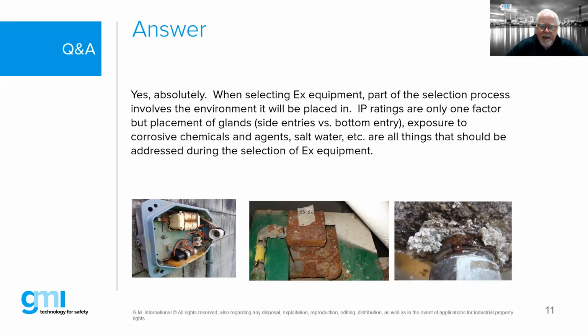Obviously, in the example on the left-hand side, a light fitting was leaking or something happened, so we had some corrosion on the inside there. The picture on the right-hand side is a nickel-plated brass gland, or actually, I don't know if it was nickel-plated or not, going into an aluminum enclosure, and you can see that you had some serious chalking. This is a big issue with cable glands going into aluminum enclosures in a high saltwater environment. So you can start to see degradation very quickly if we don't provide suitable protection, either thread lubricants, or avoiding dissimilar metals, or using metals that are really suitable for the environment. So we have to take all that into account as well.